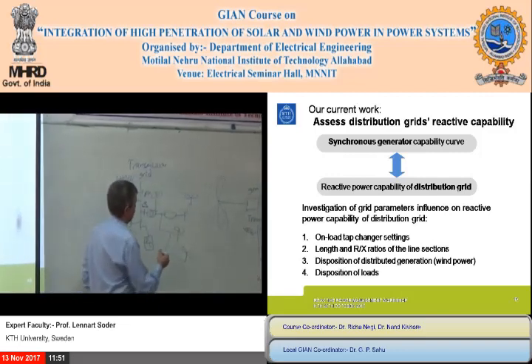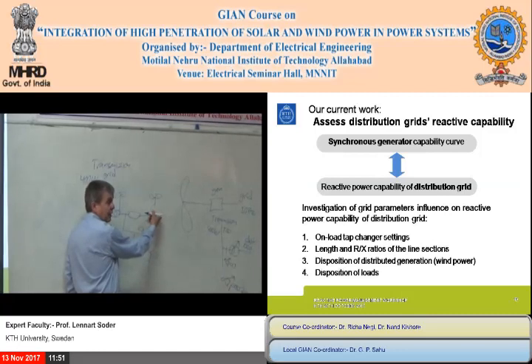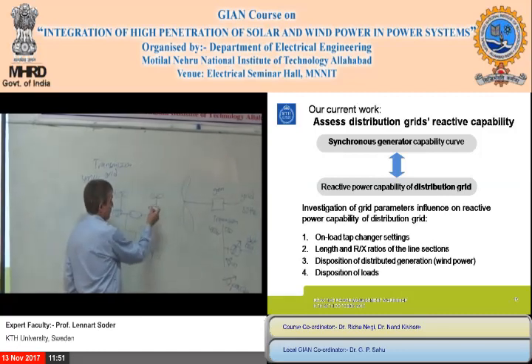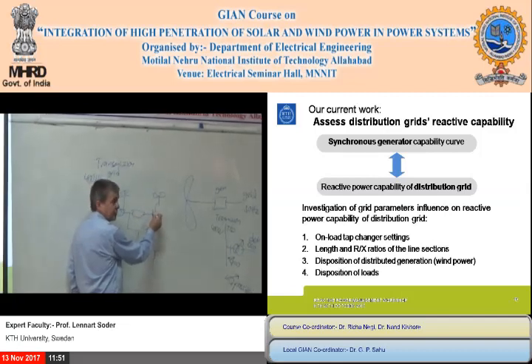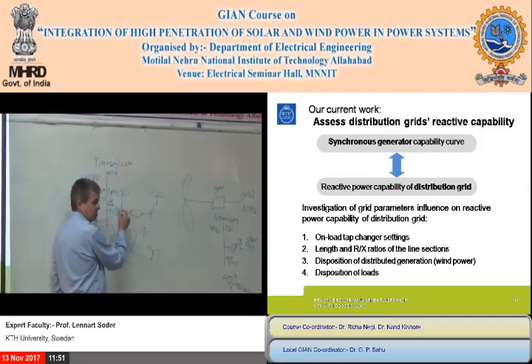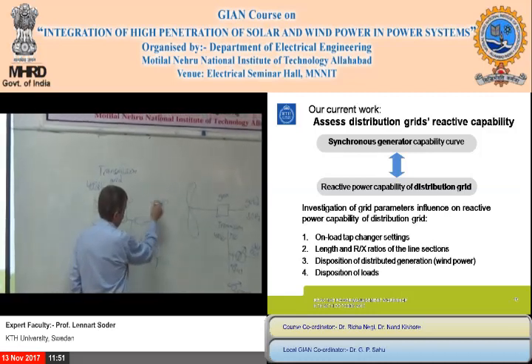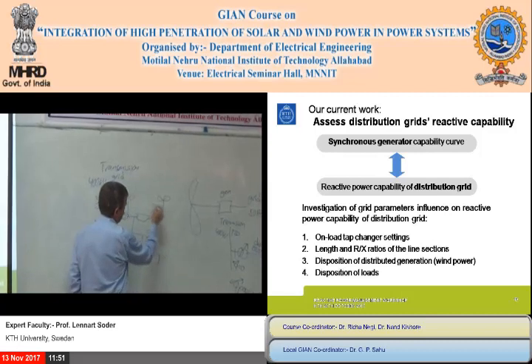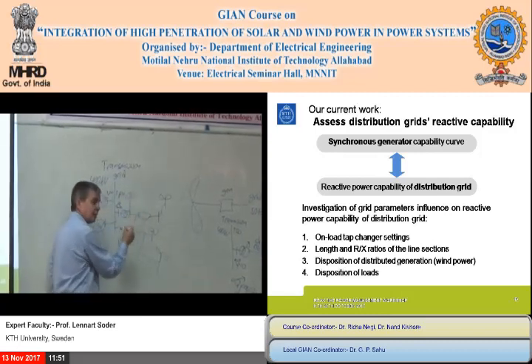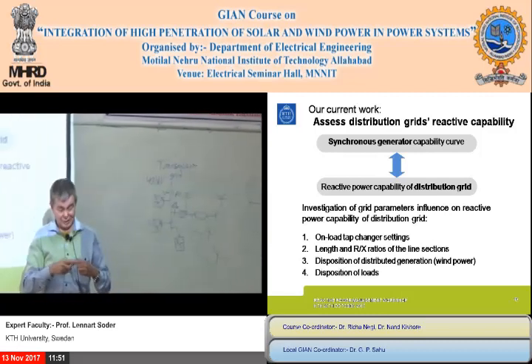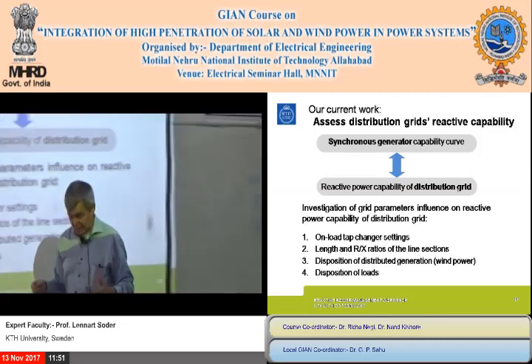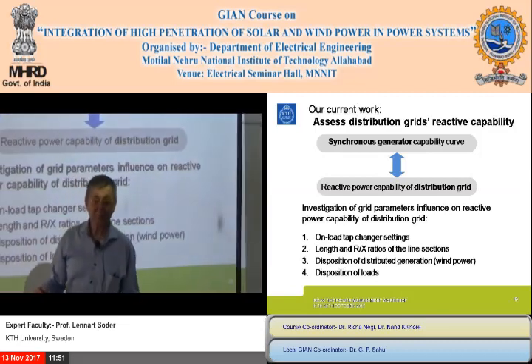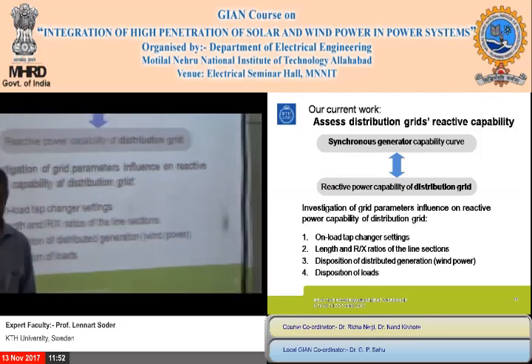If you start to produce a lot of reactive power here, with a huge amount of wind power producing, the voltage increases and you get high voltage. But you can decrease the voltage using the tap changer. So you have to coordinate the wind power's reactive power production with the setting of the on-load tap changer transformer.